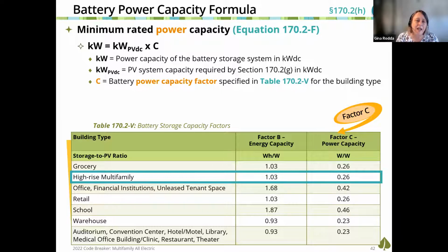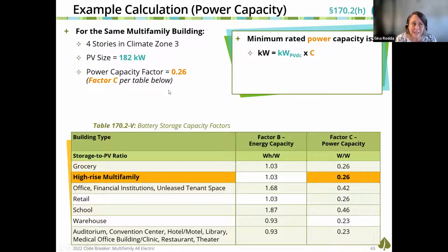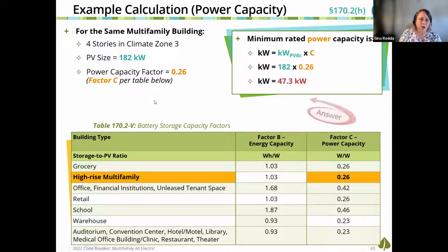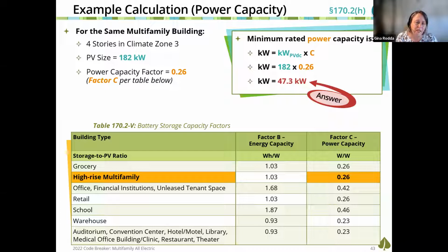We had only done half of our specification for a battery. The other half is the power capacity, in which you take that PV per kW number and multiply it times the factor associated with your building type. That becomes the second part of your battery specification, the kW sizing associated with that battery.